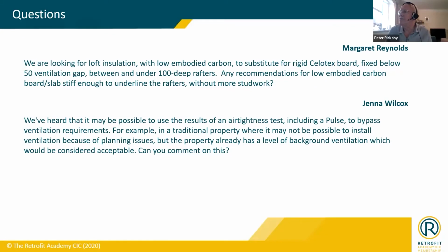And one of the problems with the new Part F is that it gives the installer or whoever a perverse incentive, because it gives them incentive to keep the building leaky or to make it more leaky in order to avoid properly improving the background ventilation in a controlled way. So I would agree with Alan that it's not possible to do it the way described.